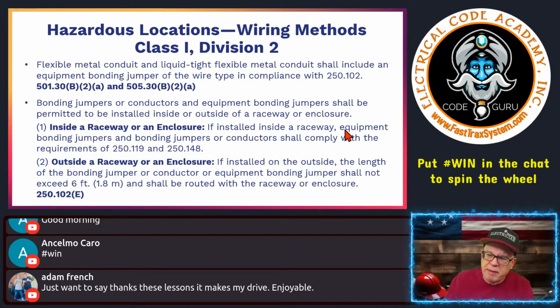Well, inside a raceway or enclosure, if installed inside the raceway, which is typically where we'd see it, equipment bonding jumpers and bonding jumpers or conductors shall comply with the requirements of 250.119, okay? And 119 is talking about how you identify it, green, whether it's bare, all those type of things. That's an identification. And it talks about the requirements of 250.148 about making certain connections and making it to boxes and stuff. And I will show you that so that you kind of have a better understanding of that. So 250.148, I'll show you.